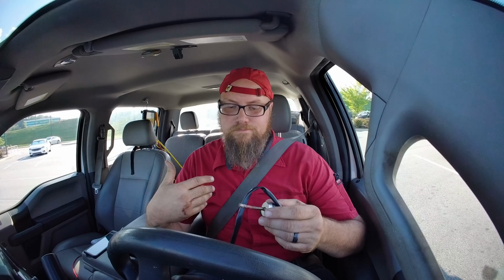I've actually come across them before where the indoor unit's not even running and the outdoor unit looks almost right. You're sitting there scratching your head, well, this is weird, what's going on? And then go inside and think, blower's not running, okay. So that is something to watch out for, and when you're charging these guys, be aware of that, because we can add refrigerant to it and it'll look almost right, because now we've got an expansion valve operating and we have a compressor and a condenser fan that's modulating to try to hit optimum output. So you can actually have them look quite right when they're not.